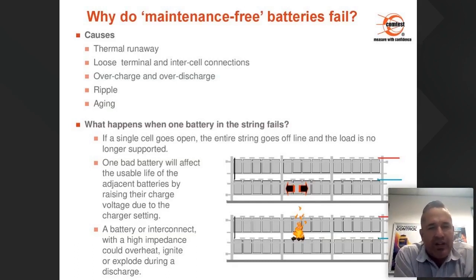If a single battery or cell goes open, the whole string goes offline and the load is no longer supported. This means that we can have 60 batteries, and only one of them needs to fail and the whole system is down. One battery will affect the usable life of the adjacent batteries by raising their charge voltage due to the charger setting. So obviously, if one battery fails, the charger is bypassing it and will then go into the next batteries, affecting their charge performance.